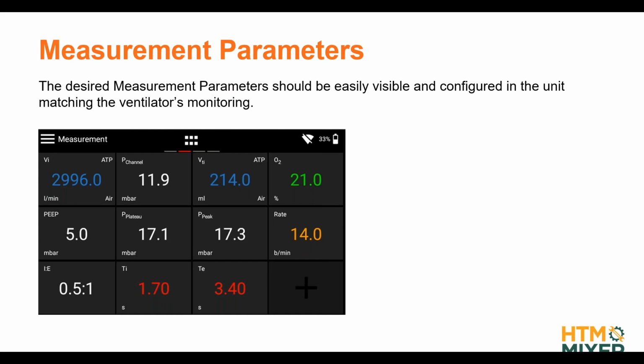Gas flow analyzers can typically measure up to about 25 different parameters. So it's important for our specific application that we know the terminology, what we are looking at, and then also set it up correctly. All the parameters can typically also be measured in different units of measure. For example, pressure on your gas flow analyzer can be displayed in millibar, centimeters of water, PSI, Pascal, whatever. So make sure that you have it set up as per your device under test, so you are comparing the right units of measurement. All right, so that was about the challenge of having the correct settings for your application.